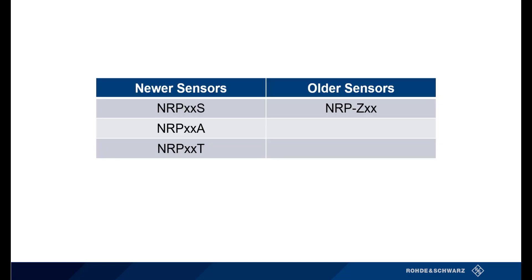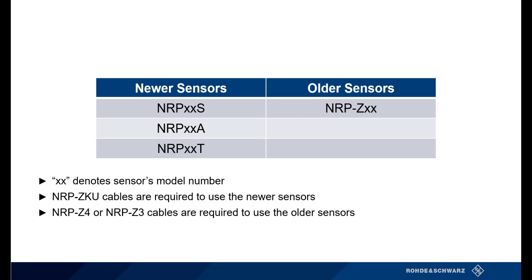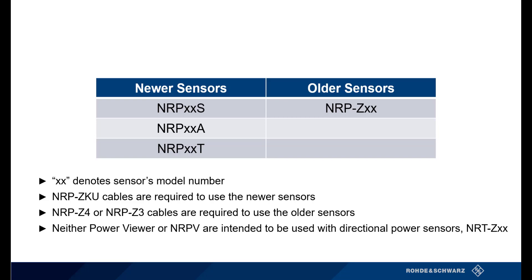Before we move forward, let's discuss the sensors that fall into the newer and older series. The table on the screen shows the variety of sensors that are in each category. The double X's distinguish the model numbers of the sensor. You must purchase USB cables to properly interface with both the newer and older sensors. The newer sensors require NRP-ZKU cables, while the older sensors can be used with either the NRP-Z4 or NRP-Z3 cables.